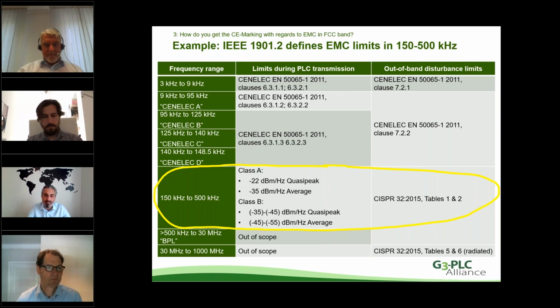In the case of 150 kilohertz to 500 kilohertz, we have a distinction between class A and class B, depending on where the device is used. And we also have the limits, quasi-peak and average. This is based on the methodology of how the limits are measured. And we also have the out-of-band disturbance limits referred to the CISPR 32 table.